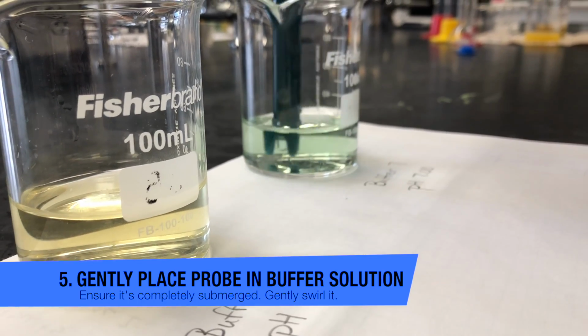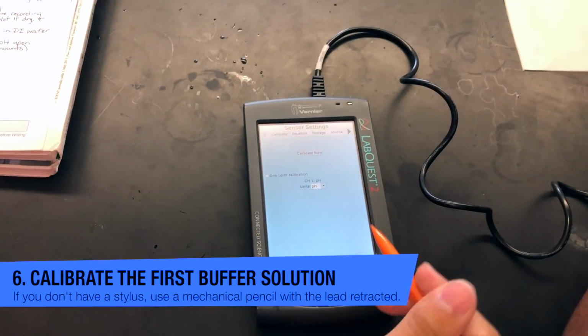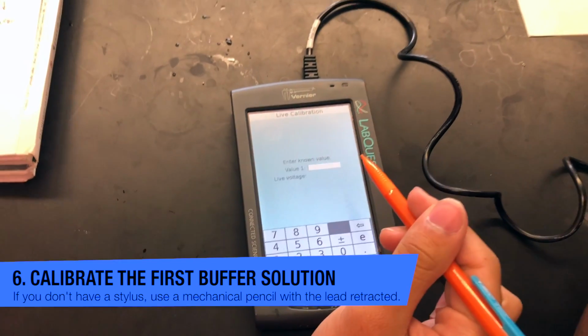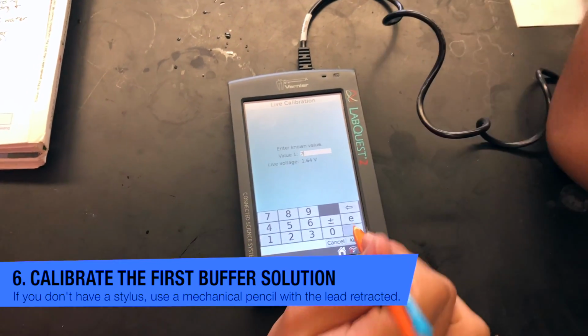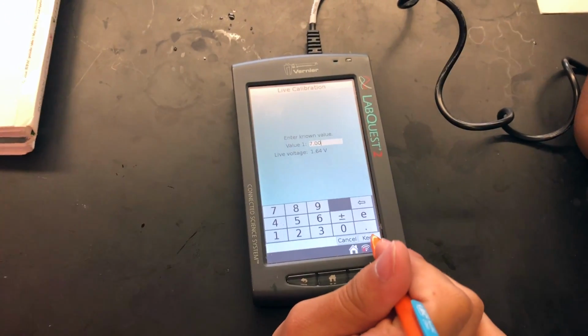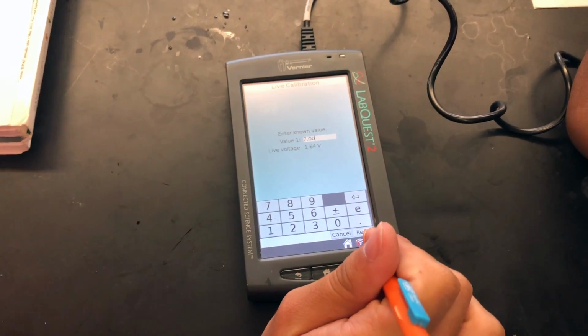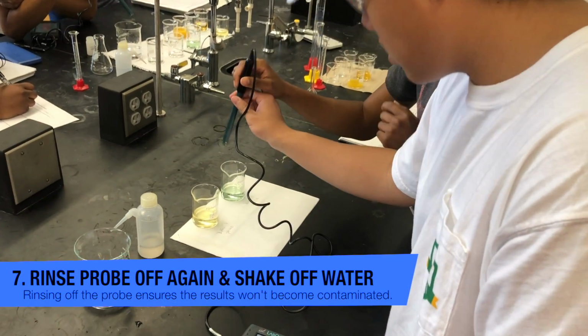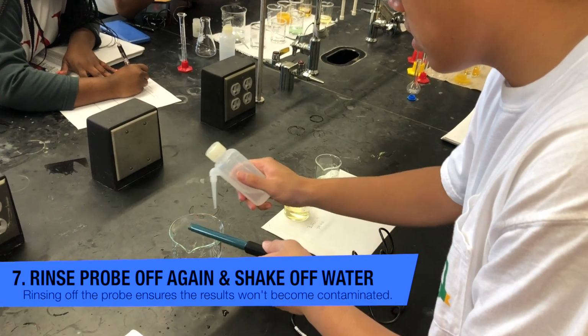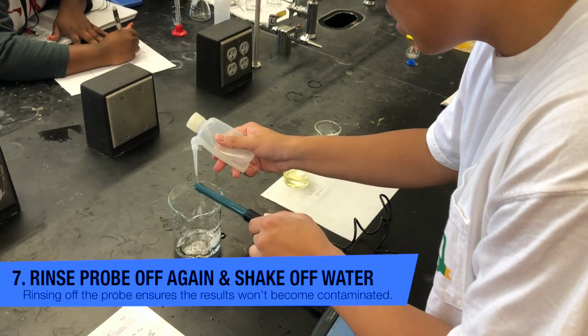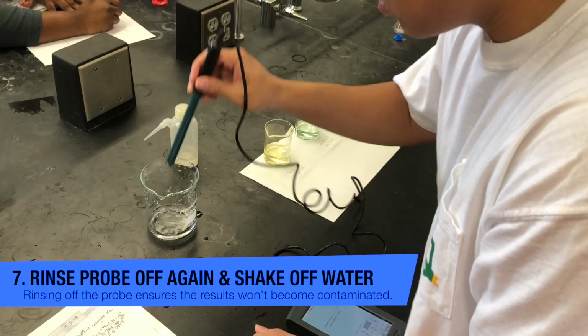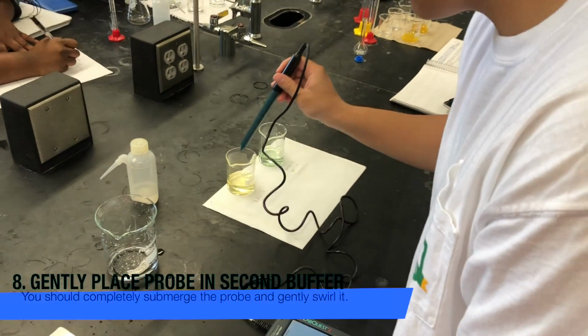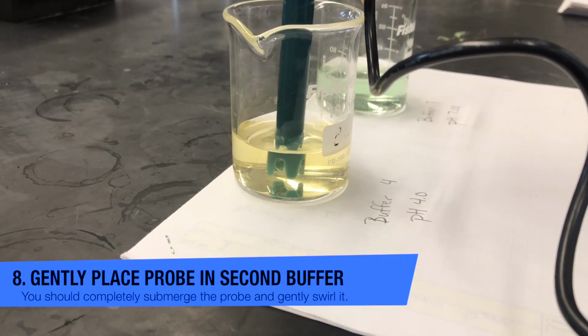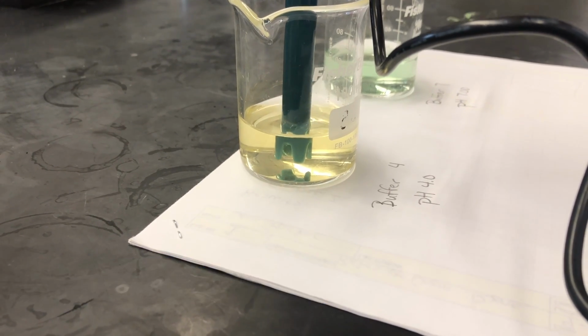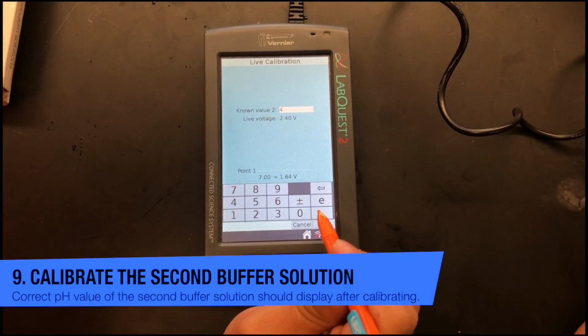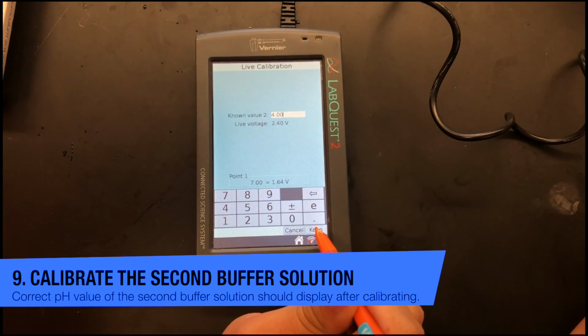On the LabQuest, you can now begin calibrating. If you don't have a stylus, you can use a mechanical pencil with the lead retracted. Once the voltage value has stopped changing, you can enter the pH value of the buffer solution. Rinse off the probe and gently shake off the excess again. Now, submerge the probe into the second buffer solution and gently swirl. Enter the second pH value, tap Keep, and then tap OK.